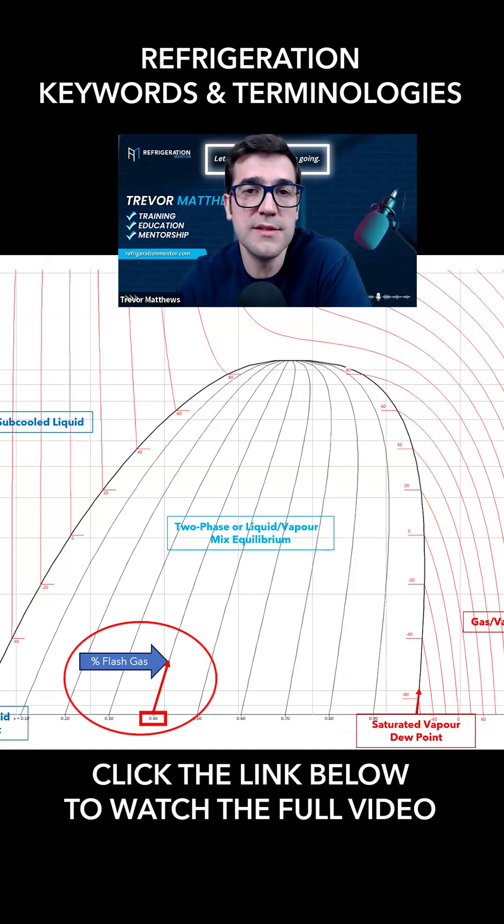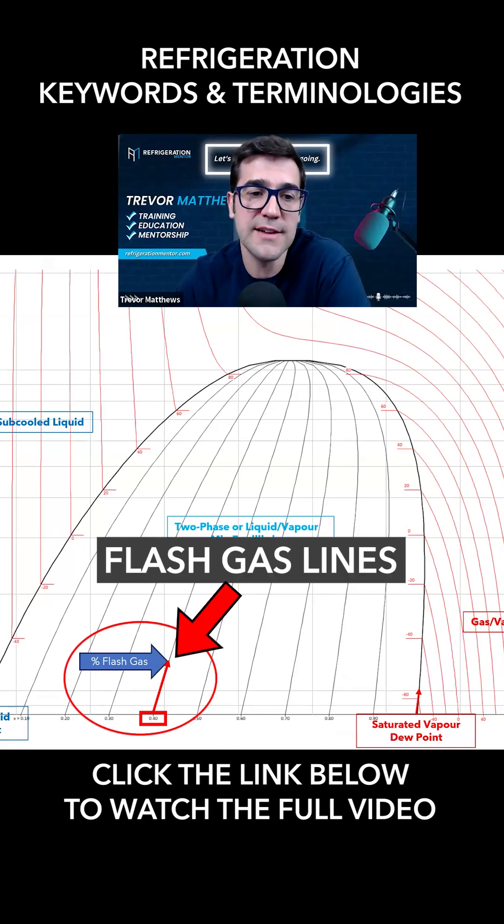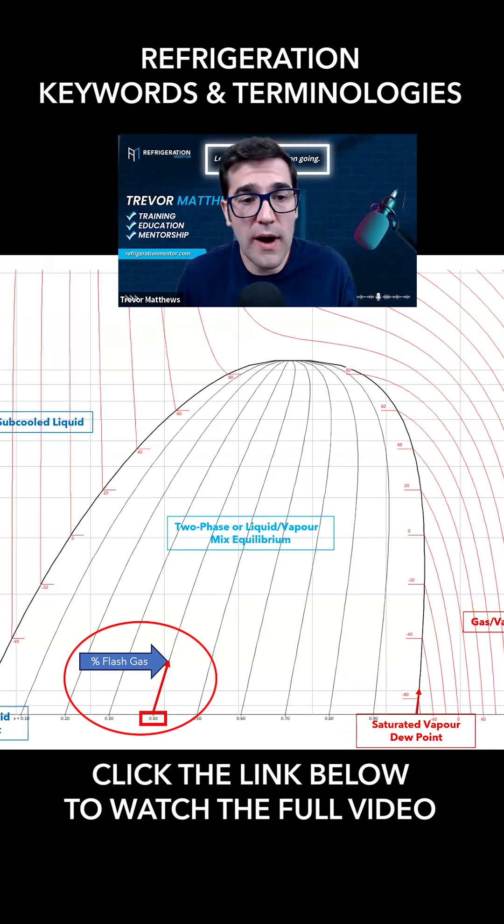Inside these, there's these lines here called the flash gas lines, the percentage of flash gas lines. This is really important to understand how much flash gas is in that receiver or coming out of that high-pressure valve, coming down the drop leg from the condenser. This is super important because it's going to tell us how that system is running.